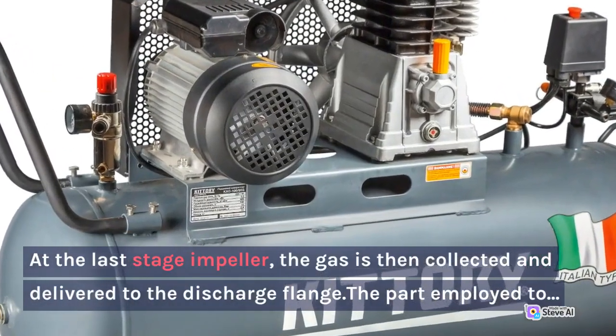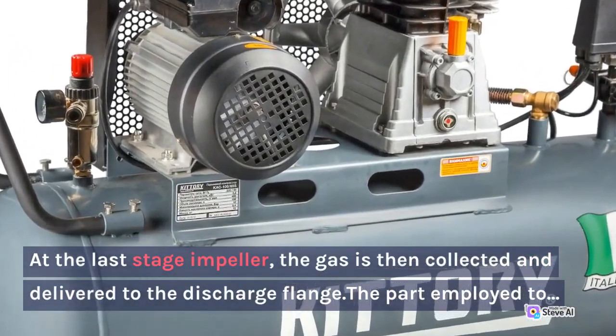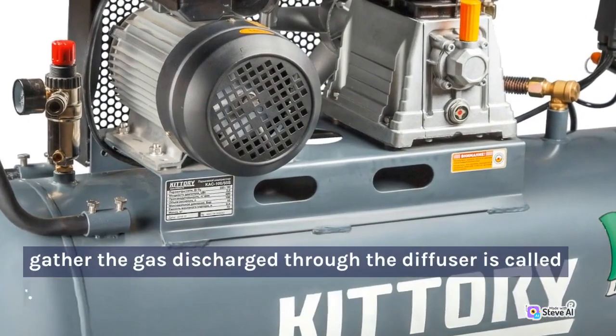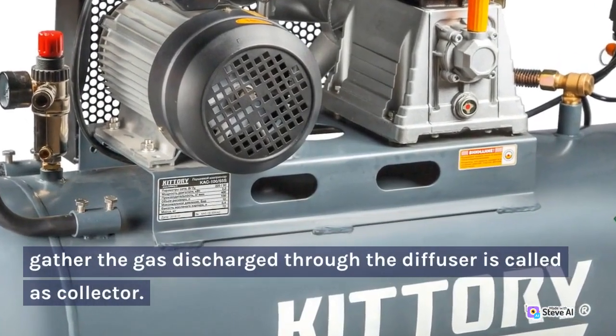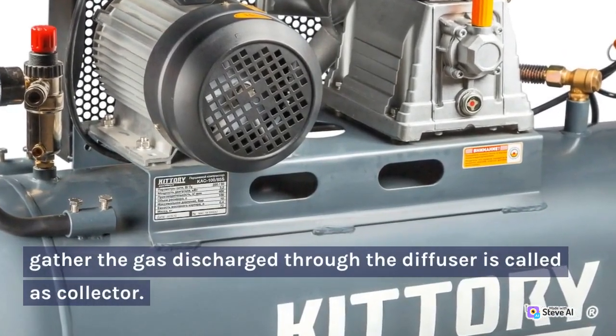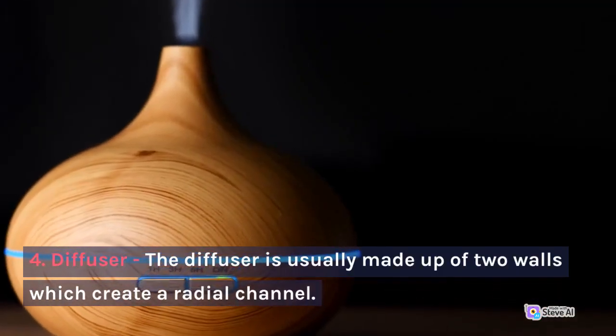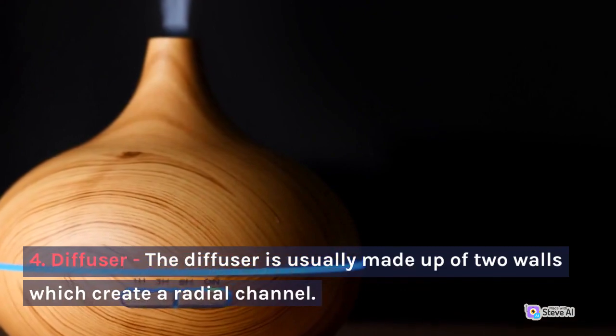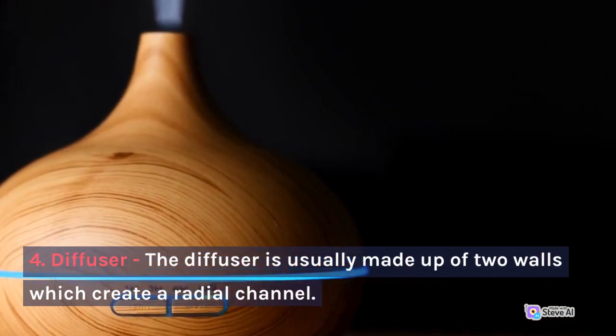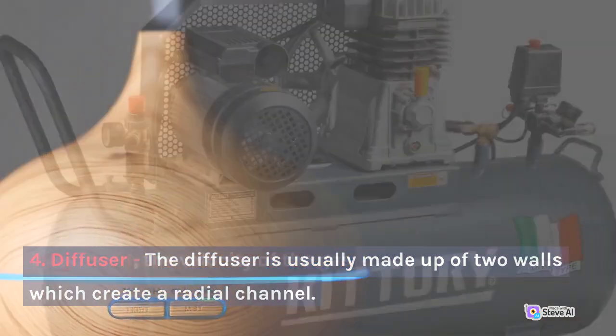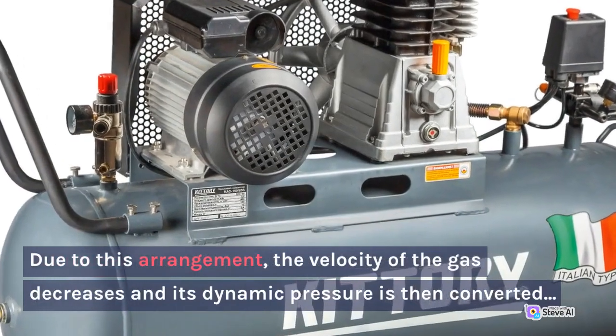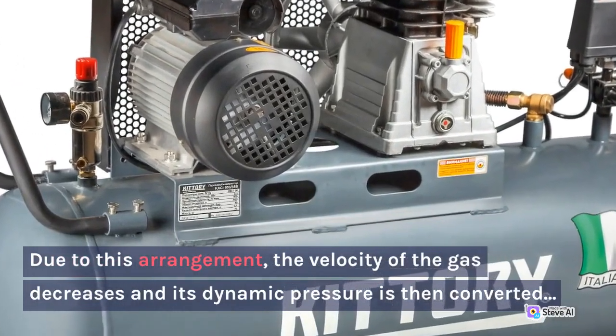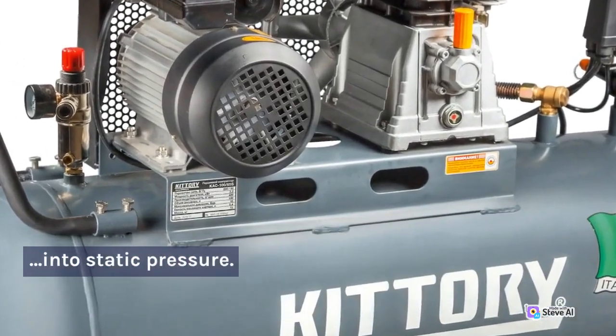3. Collector. At the last stage impeller, the gas is then collected and delivered to the discharge flange. The part employed to gather the gas discharged through the diffuser is called its collector. 4. Diffuser. The diffuser is usually made up of two walls which create a radial channel. Due to this arrangement, the velocity of the gas decreases and its dynamic pressure is then converted into static pressure.